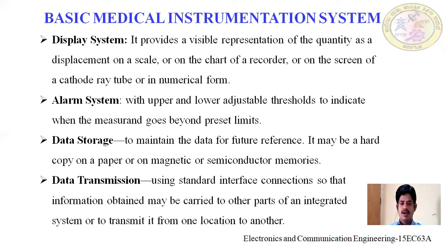Then we have an alarm system with upper and lower adjustable thresholds to indicate when the measurement goes beyond the preset limits. It means we should have some alerting system. We should have a threshold to indicate if it is going below the threshold level.